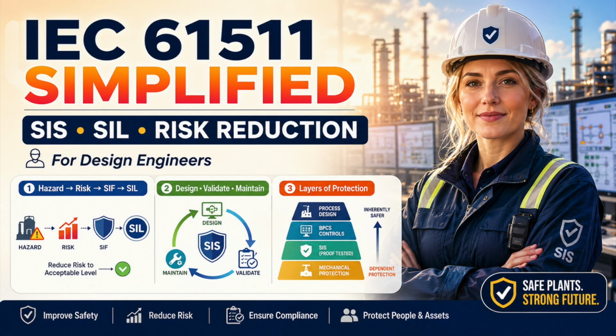Has it been tested? Idealized human reliability has no place in a serious risk assessment. Startups, shutdowns, maintenance, utility failures, manual control, commissioning, cleaning, purging, and abnormal lineups must also be considered. Many hazardous events do not occur during stable normal operation. They occur when the process configuration is changing and the workload is high. A safety function designed only around steady-state operation may be weakest when the plant is most vulnerable.